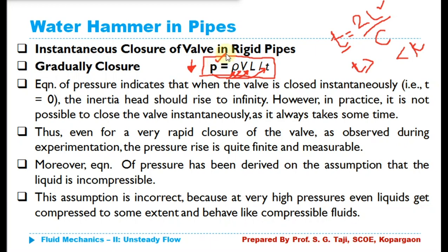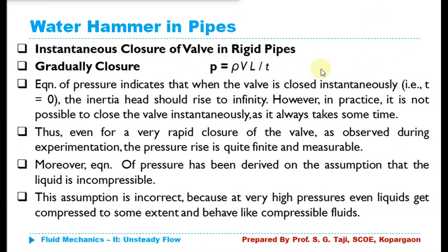You can increase the time for closing the valve. It may not be practically possible in most cases, but by controlling this time we can minimize the water hammering effect. Now look at this equation. T is in the denominator, so if I put T equal to 0, anything divided by 0 gives infinity. So the value of P in that case will be infinity.